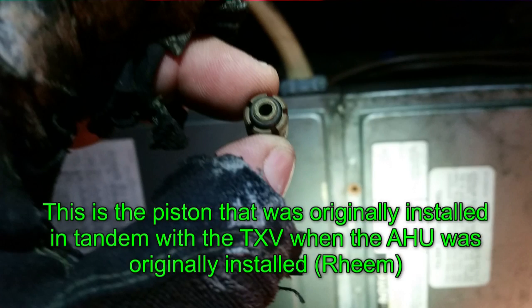Be aware of it — this will make the machine perform a little bit better, getting a little bit more refrigerant into the coil, because it is a big difference between the piston they put in there on their coils for the TXV and what you would normally put in as far as a piston. Let's take a look and enjoy.